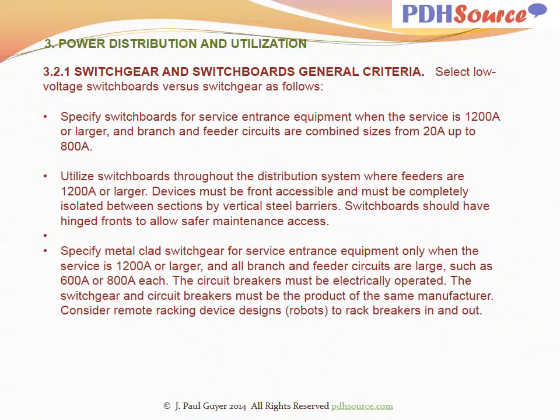Specify metal-clad switchgear for service entrance equipment only when the service is 1200 amps or larger, and all branch and feeder circuits are large, such as 600 amps or 800 amps. The circuit breakers must be electrically operated. The switchgear and circuit breakers must be the product of the same manufacturer. Consider remote racking device designs, robots to rack breakers in and out.